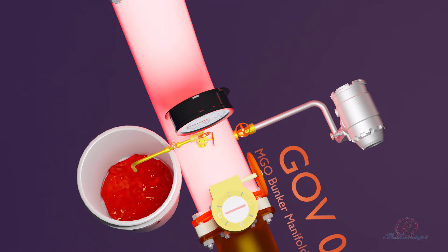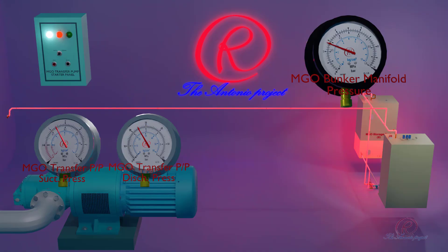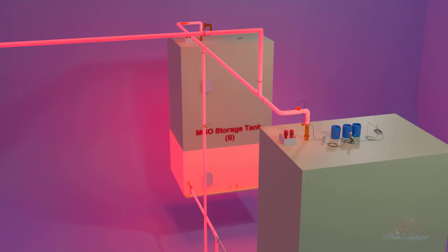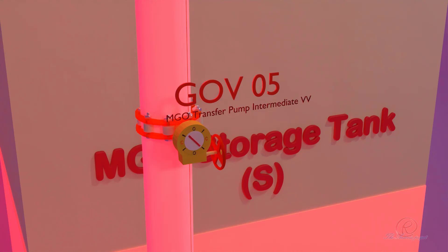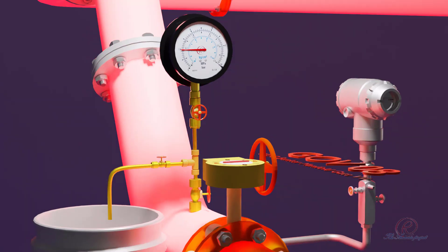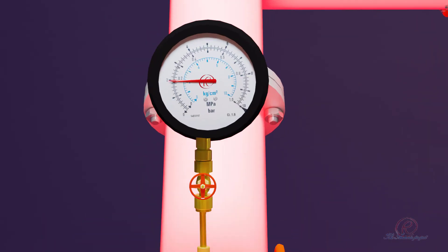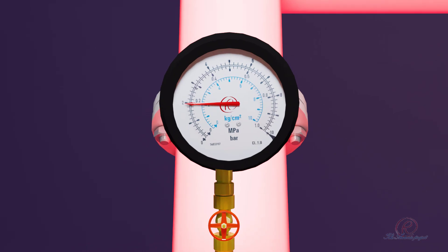Carefully monitor discharging pressure and regularly check joints, flanges, and dresser fittings for any leakage. Allocate enough personnel to carry out regular patrols during filling of the bunker pipeline. After stopping the MGO transfer pump, close GOV-05 MGO transfer pump intermediate valve to isolate pressure on the bunker piping line. Check the bunker manifold pressure; currently it reads 2 bar on the analog pressure gauge and 1.98 bar on the digital pressure transmitter.